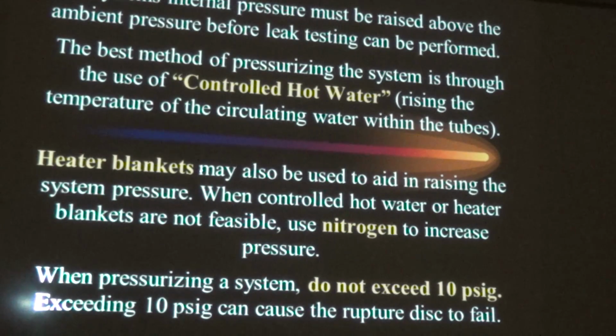The system's internal pressure must be raised above ambient pressure before leak testing can be done. The best method, and here's the test question, of pressurizing the system is through the use of controlled hot water, raising the temperature of the circulating water within the tube. Heater blankets may also be used to aid in raising the system pressure. When controlled hot water or heater blankets are not really usable, use nitrogen to increase pressure. When pressurizing the system, do not exceed 10 psig. Exceeding 10 psig can cause the rupture disc to fail.